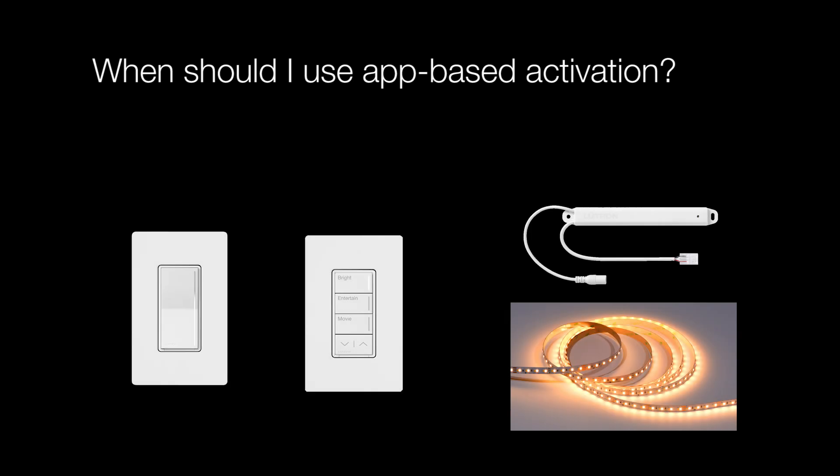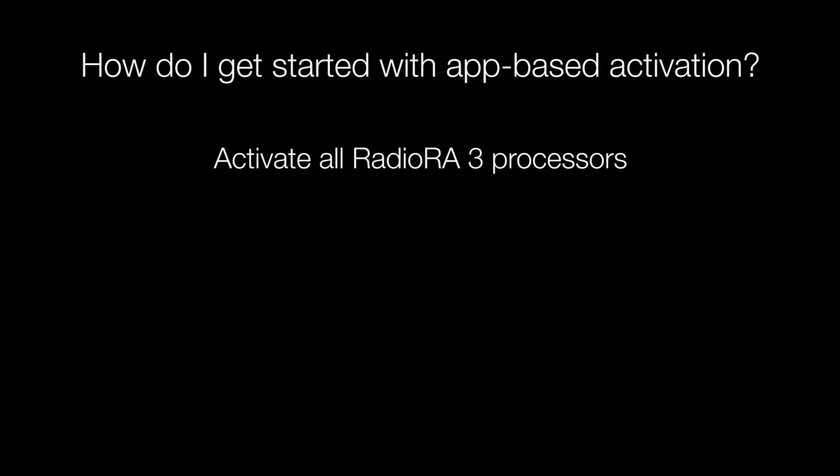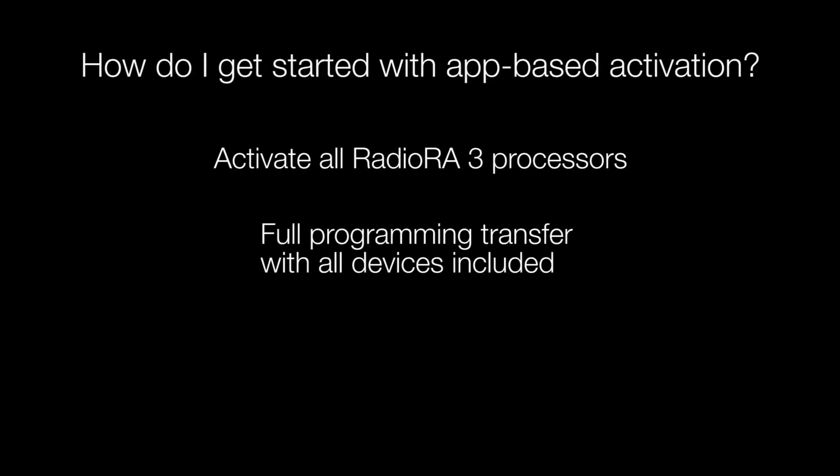App-based activation is used for Clear Connect Type X devices, such as Sunnata Pro dimmers and Lumaris tunable white tape lights. Prior to activating devices, the system processors must have been activated and received a full programming transfer that included all of the devices you're intending to activate.